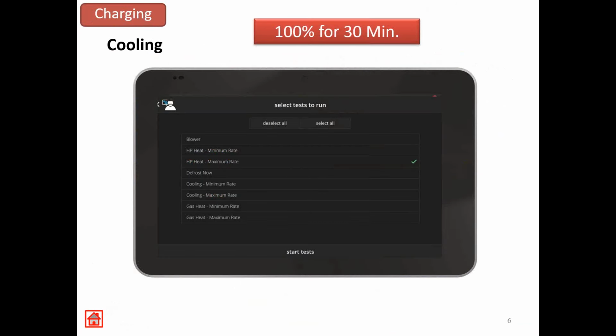All right. I want to go back over this just real quick. Make sure that we understand setting on a 20 or 25 or any variable capacity unit. You have to ensure that the compressor is running at full rate. And this is where you do that from the dealer portal inside the control screen. You want to go to the test function and you'll be able to set that from there. That's the only way we can get the 100% capacity up and running.